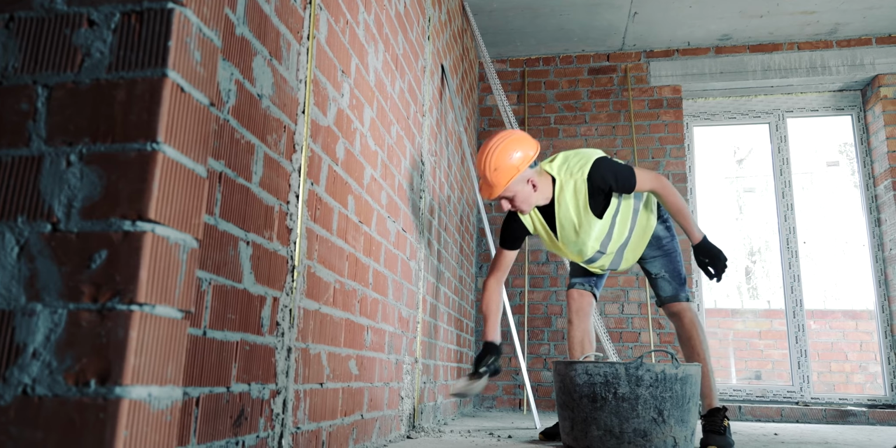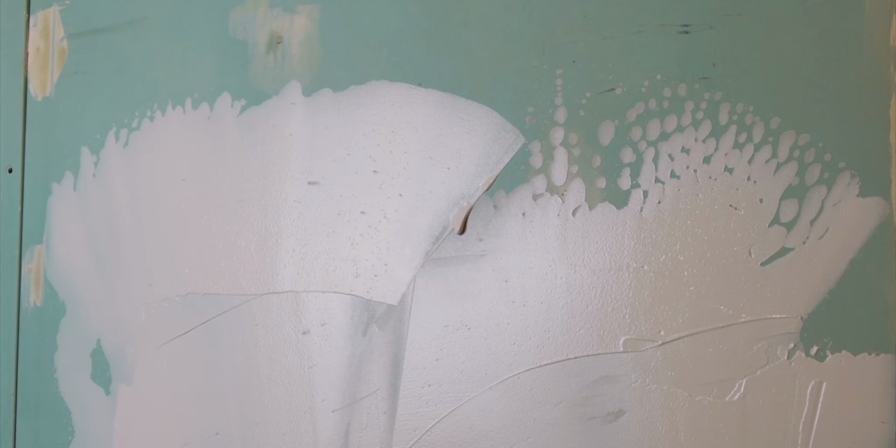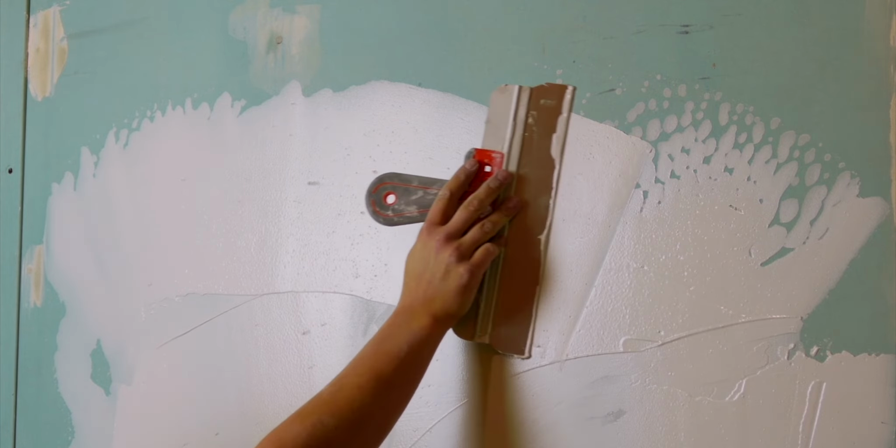And there are some key aspects to the construction methods specific to this house that have helped a lot with that. It's got a solid floor downstairs. Right. And it's got the traditional plaster. Sadly, a lot of the new build houses now all use the dot and dab plaster method. Right. So there's a gap behind the plasterboard and the blockwork, and it doesn't seal up. Right. And all the warm air flows through the building envelope and outside, and leaks like a sieve.